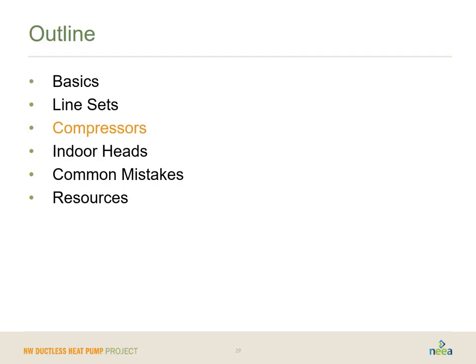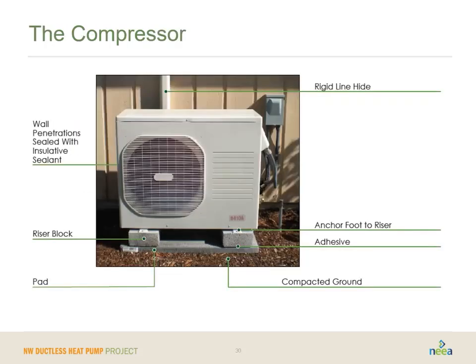Next, let's talk a little bit about the compressors themselves. So here's your typical outdoor compressor, also known as the outdoor unit. Some of the things we're pointing out here: the wall penetrations have been sealed with an insulative sealant. Again, it's really going to fill all the gaps and make sure that you're not going to get air, moisture, or insects coming in. You'll see the rigid line hide. It looks almost like a downspout there. It's usually a plastic or aluminum cover that snaps over your line set. And again, this really gives you both better looks as well as better protection of that line set. You'll see there's a pad on the bottom of this one. They made sure they compacted the ground first. So getting compact ground so this won't settle or tilt, then putting the pad on it, is a great first start.